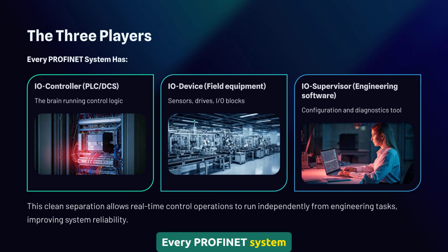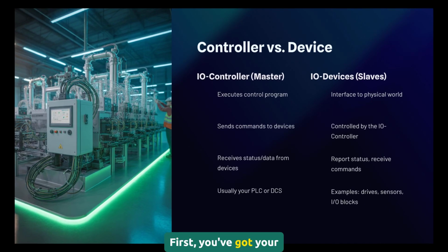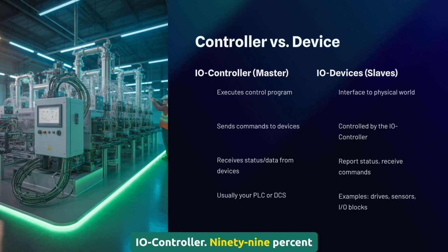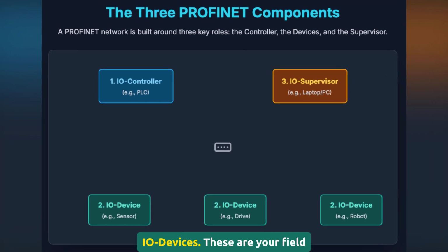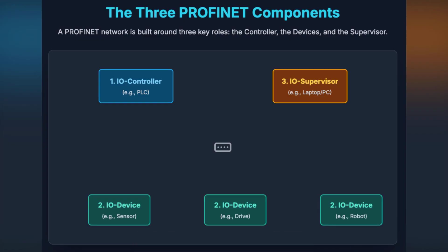Every PROFINET system has exactly 3 types of players, and understanding these roles is absolutely critical. First, you've got your I/O controller. 99% of the time, this is your PLC. It's the brain that runs your control logic and coordinates everything else. Second are your I/O devices. These are your field devices, your I/O blocks, motor drives, sensors, and anything that interfaces with the real world. They're controlled by the I/O controller.